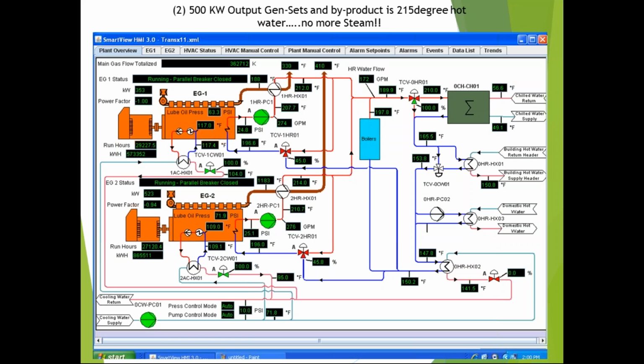But I'm choking back. I'm sending back 45% of the water in volume that's coming out of my engine block right back into it. Something's wrong there. So what could have been designed different? Could this jacket water system have been designed with enough volume, piping size, to where it goes through a short cycle of piping infrastructure locally and then through one big long heat exchanger and just transfer that heat? And I'm flowing 100%, right? I'm out of here. I'm into this long heat exchanger. I'm right back into it full bore instead of being choked.